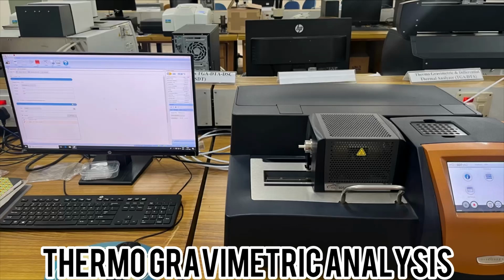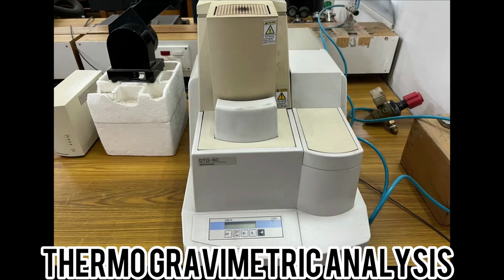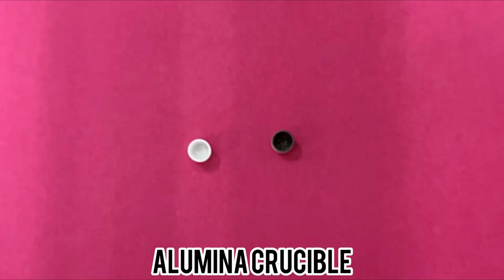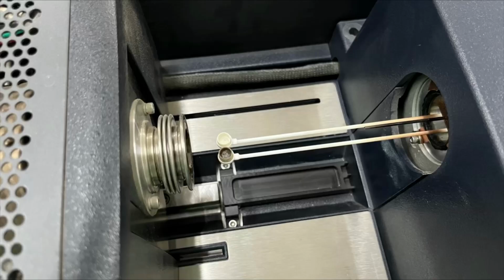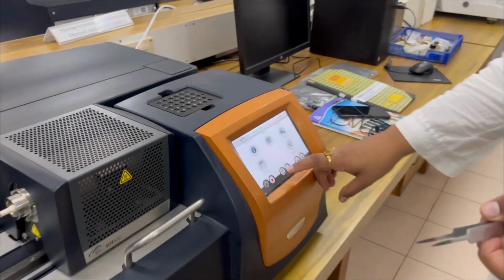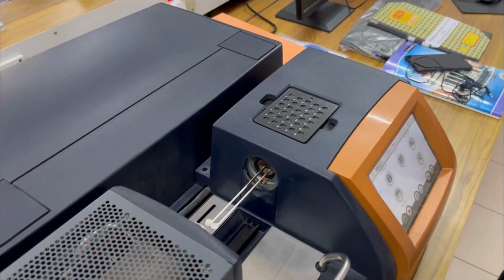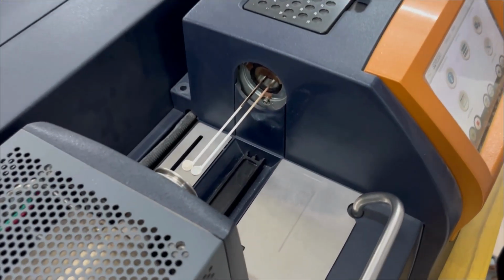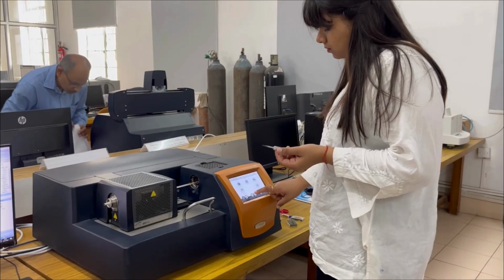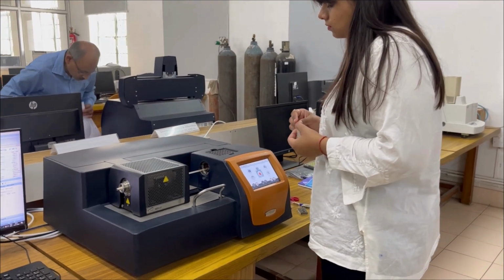TGA measures weight or mass change as a function of time, temperature, and atmosphere. It determines the composition of materials and predicts their thermal stability. It involves subjecting a sample to a controlled temperature increase or decrease while continuously monitoring its weight. There are 2 crucibles, one for the sample and the other for reference, which is kept in a furnace for controlled heating.